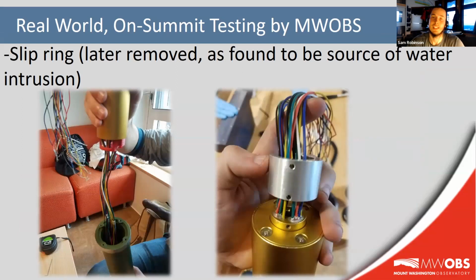So in the summer of 2019, a few months after that 171 event, the pitot did come back down from the instrument tower for some more small modifications. A few internal parts were upgraded to help improve the performance and durability of this instrument. An internal water issue was figured out with the slip ring, which is pictured here, and it was resolved, as well as upgrading the pneumatic tubing and connectors at the same time. This allowed for even less tubing in the body of the anemometer and a better fit for everything inside the tail fin. So in a nutshell, this shows that while initial testing is super important and can be helpful, real world testing is the most important. We were able to resolve these initial issues while also improving the design even further than originally designed and manufactured. So it was definitely a win-win.